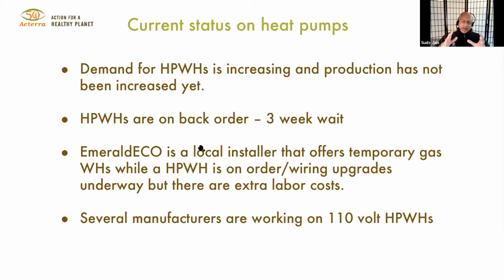As I mentioned, that 220 volt service means you have to run extra electricity to your water heater location, but you have 110 outlets all over your house. So there are some water heater manufacturers looking at 110 volt heat pump water heaters. They'll heat the water much more slowly than the 240, so you might want a bigger tank so you don't run out of water. But over the course of a whole day, they'll provide enough heat, and you can just plug it into an outlet using a regular breaker. So we're trying to get manufacturers to do that.